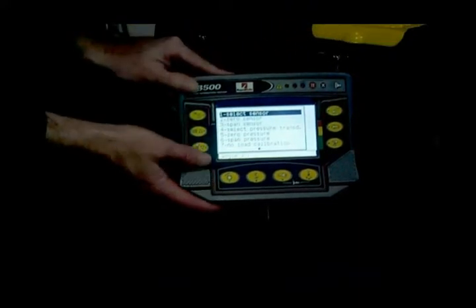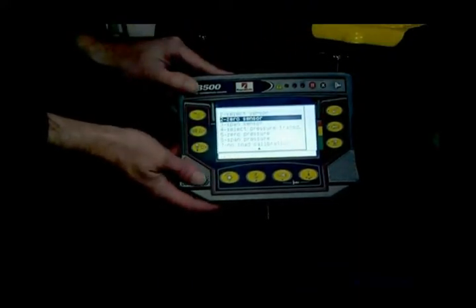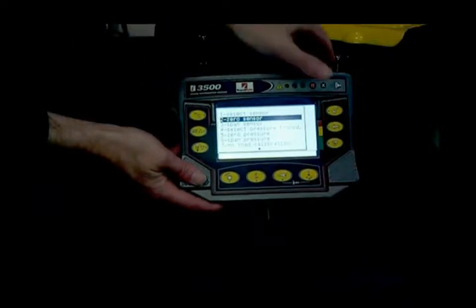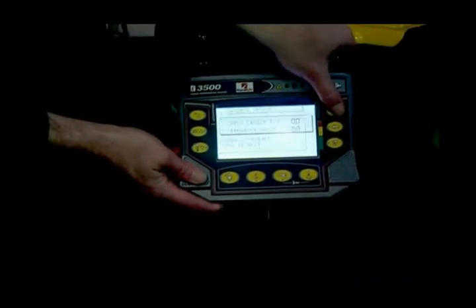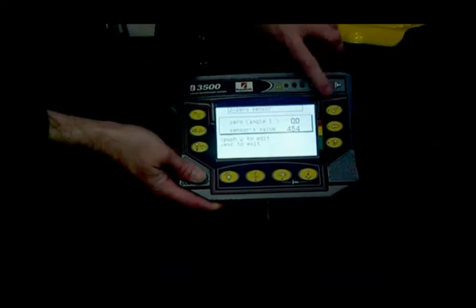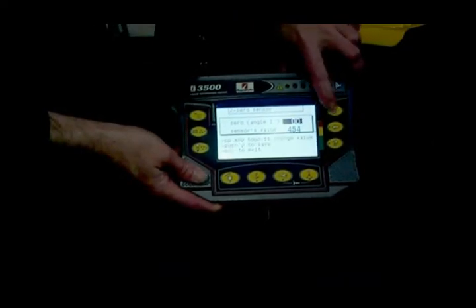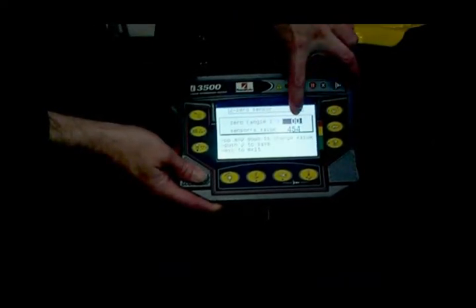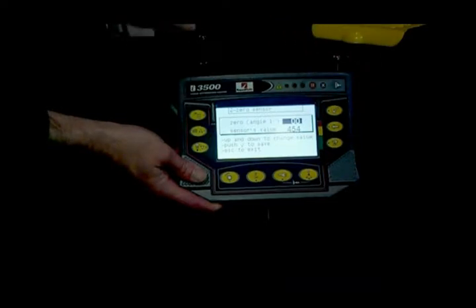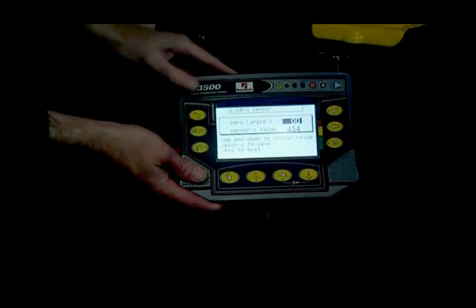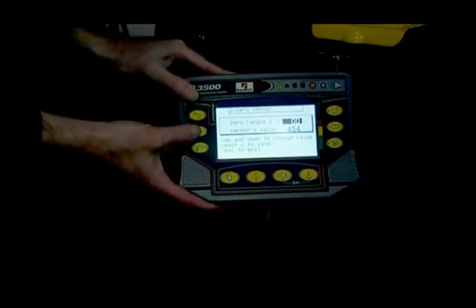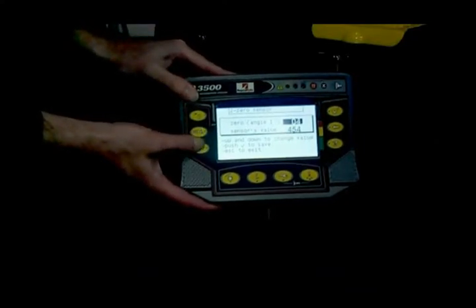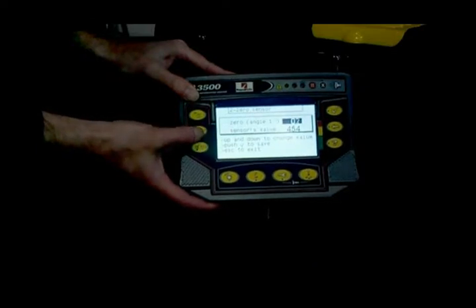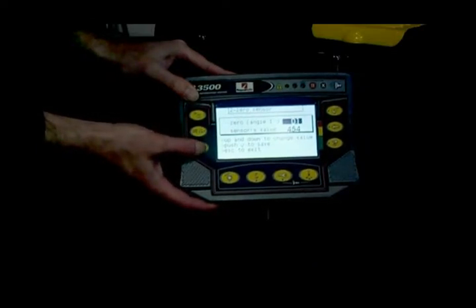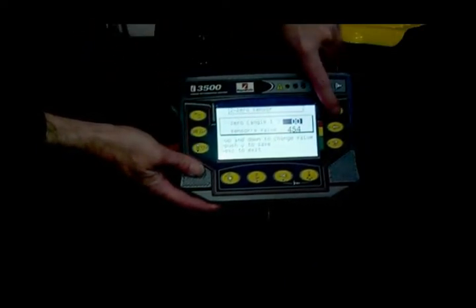Now it's ready to calibrate the angle sensor. We're going to come down, hit select zero sensor, and hit the check mark. And what we're going to do here is hit the check mark one more time, and it's going to highlight this block right here. And that is where I would now enter the angle which I measured off of my digital level. And you do that by scrolling up or down with these two buttons. Once you have the value that you want, you can go ahead and hit the check mark.